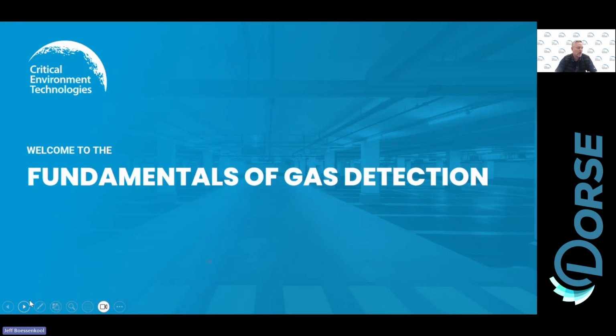So I wanted to just talk a little bit about some of the critical environment alarm suggested set points. One of the reasons I bring this up at this point of the conversation is that those organizations make recommendations for alarm levels and set point levels, and we take that information and publish it in our Introduction to Gas Detection study guide, which I will forward out after the call. I'll send out an email to all the attendees with a link so you can download this study guide. But this here on the screen is a snippet of that study guide, and this talks about our suggested gas alarm set points based on those regulatory authorities, okay?